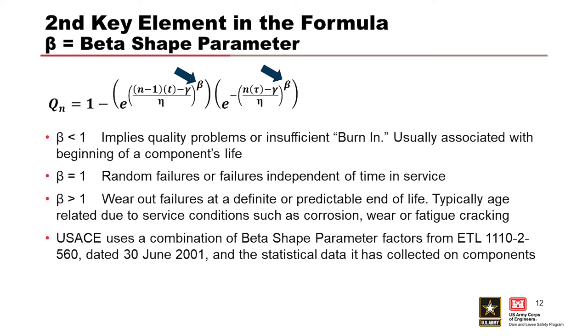A beta greater than one is wear-out failures at a definite or predictable end-of-life. Typically, age-related due to service conditions, such as corrosion, wear, fatigue, cracking. We use a combination of beta parameters from ETL 1110-2-560 and the statistical data that we've collected on components.